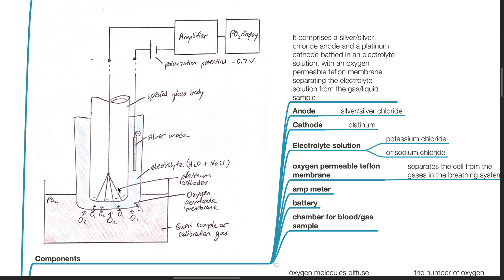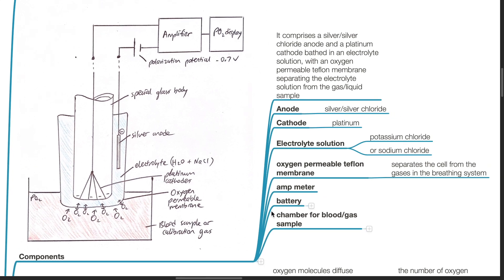The anode is made of silver or silver chloride. The cathode is made of platinum. The electrolyte solution is potassium chloride or sodium chloride. An oxygen-permeable Teflon membrane separates the cell from the gases in the breathing system. Additional components include an ammeter, a battery, and a chamber for blood or gas sample.